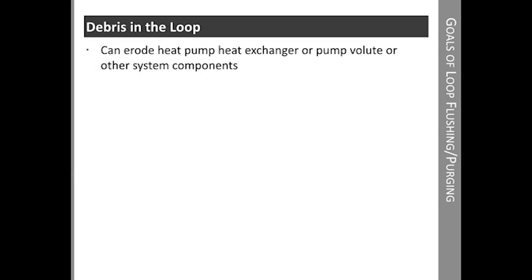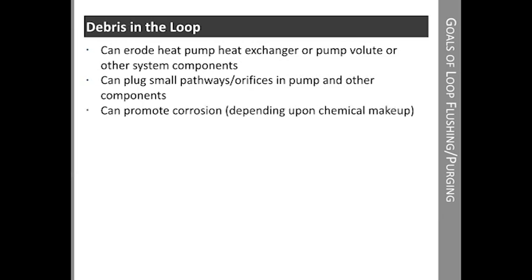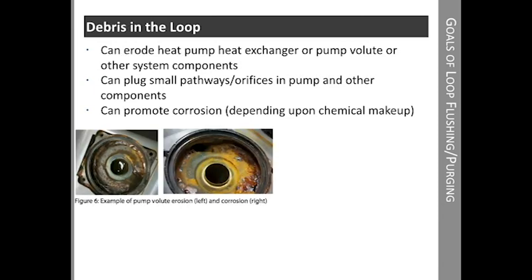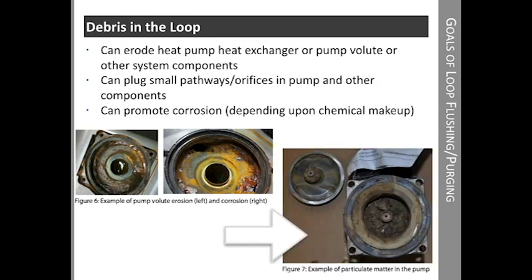Now that we've discussed the problems with air in the loop, let's talk about debris in the loop. Debris in the system can become abrasive. It may erode the heat pump exchanger, pump volute, or other system components, resulting in leaks or component failures. Debris can also plug small pathways or orifices in the pump and other system components. Depending upon chemical makeup, debris can even promote corrosion. The picture on the left is an example of erosion — you can see the wearing of the volute as sand has worn down the material. On the right is an example of corrosion in the system. This picture is an extreme case of debris in the system; in this case, the debris has resulted in the pump shaft breaking.